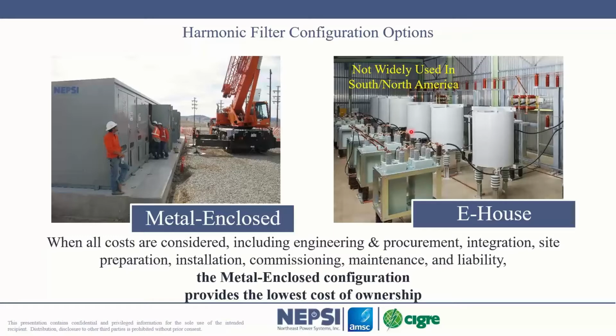The reality is some devices, especially cycloconverters, for example, their harmonic output does change depending upon the operation of the mill. So harmonics within a network do change from one point of the day to another point of the day. The harmonic filter system, however, does not change. It's a fixed passive solution.